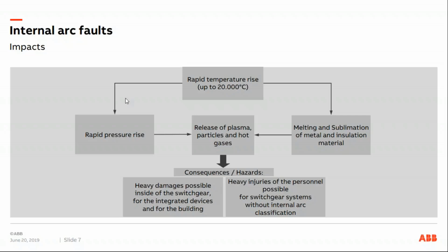So the rapid temperature rise results in rapid pressure rise and the melting and sublimation of metal and insulation material, which then again leads to release of plasma and particles and hot gases. And the consequences are heavy damages inside of the switchgear for the integrated devices and for the building, and heavy injuries for your personnel possible for switchgear systems without internal arc classification.